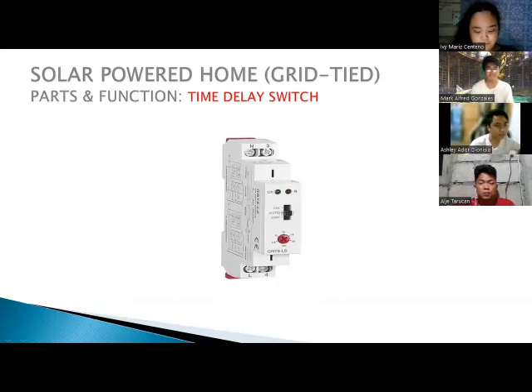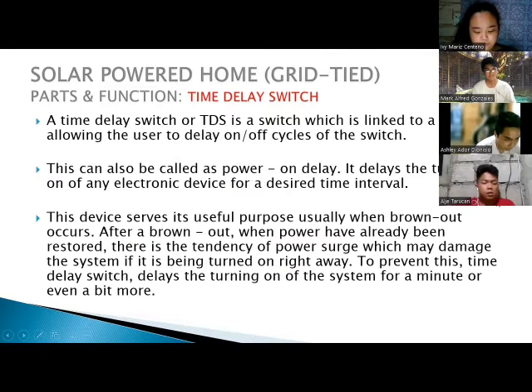Next is solar powered home grid type part and function: time delay switch. So, what does the time delay switch do? A time delay switch, or TDS, is a switch linked to a timer allowing the user to delay the on-off cycles of the switch. This can also be called power on delay. It delays the turning on of any electronic device for a desired time interval. This device serves its useful purpose usually when a brownout occurs. After a brownout, when power has been restored, there is a tendency of power surge which may damage the system if it is turned on right away. To prevent this, the time delay switch delays the turning on of the system for a minute or even a bit more.